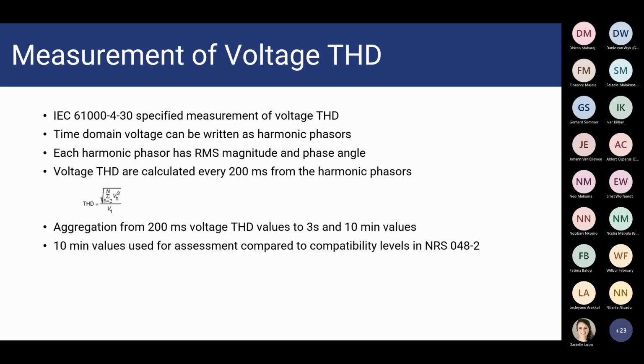Okay, so how is voltage THD measured? Firstly, it's specified in the IEC 61000-4-30, which specifies how voltage THD is measured. Time domain voltage can be written as harmonic phasors. So for each phasor, your harmonic will have an RMS magnitude, as well as a phase angle. And your THD is then calculated every 200 milliseconds from the harmonic phasors, using the magnitude and angle, and it's calculated using this formula.